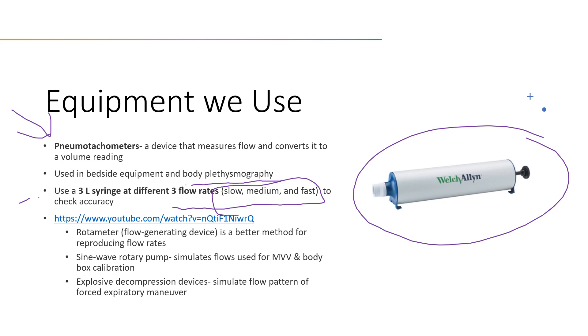Other calibration devices include the rotameter, which is a flow-generating device. Unlike the super syringe, it's automatic and doesn't rely on human power, making it better for reproducing consistent flow rates. There's also the sine wave rotary pump, which simulates the flows used during the MVV — maximum voluntary ventilation — test, where the patient breathes fast and deep. The sine wave rotary pump is useful for calibrating that test and for body box calibration.